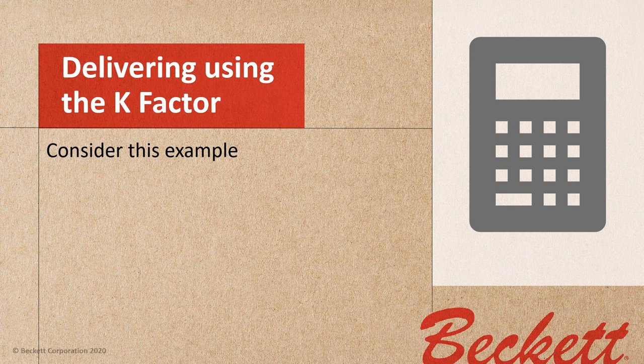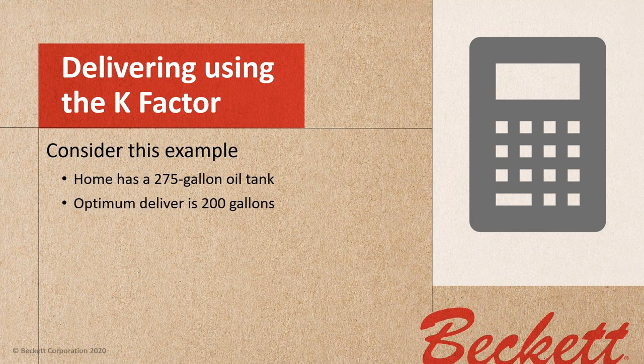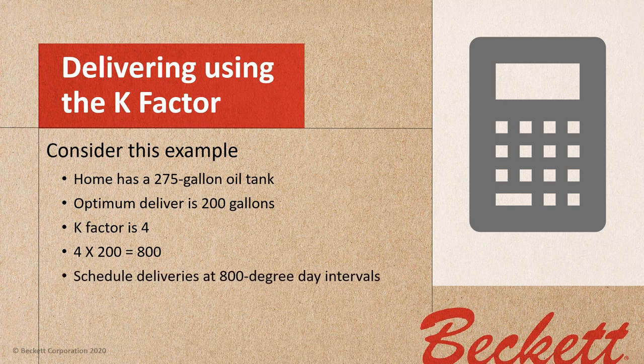Now let's look at delivering using the K-factor. The home has a 275-gallon oil tank, and the optimum delivery is 200 gallons. The K-factor is 4. So we take the K-factor of 4 times 200 and we get 800. We schedule and pull our tickets for deliveries at 800 degree days. We're just refreshing our brains with all this.